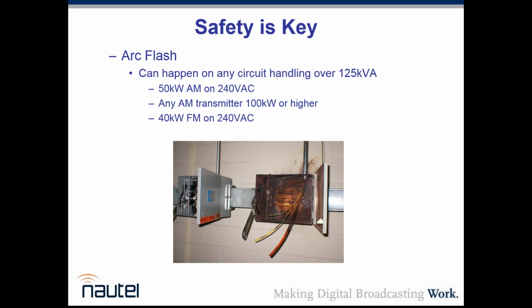So arc flash is actually a whole new subset of safety protection with separate training courses associated with it, and it doesn't make any difference whether your transmitter is solid state or tube type. Arc flash just simply means high current. And you can have problems in your breaker boxes, as shown here, but you can have problems in your transmitter. You've got hundreds of amperes running around a high-power solid-state transmitter. Yep, and ultimately what you've got to look at is the kVA consumption. I mean, if you're running a 50 kilowatt AM off 240 volts, any high-power AM of 100 kilowatts or higher, or even FM on 240, and you could go as low as a 30 kilowatt FM on 240 single phase, where you've got close to a 400 amp service.